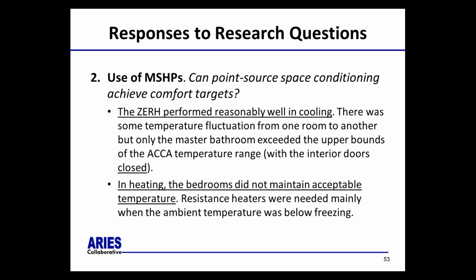Heating was a bit different. As Jordan showed, those charts indicated that House C struggled at times to maintain temperatures in the remote spaces — the bedrooms — near or within the 2-degree band that ACCA requires. With doors open, not so much a problem, but with doors closed, you start to get some issues.